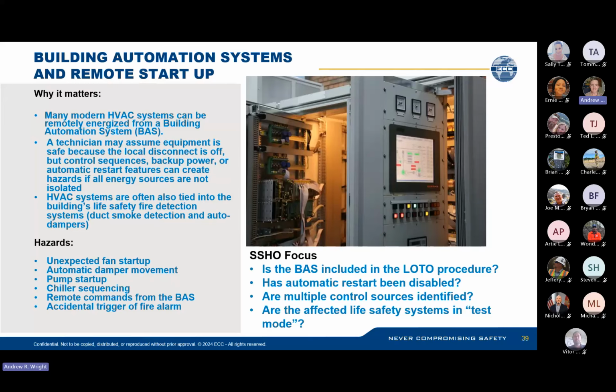HVAC systems can also be tied into the building's life safety system. A lot of times they'll have duct smoke detectors that will trigger if there's a fire, and they'll automatically shut all the dampers so that they're not pumping smoke throughout the building. And if you're working on one of those and you set it off, the fire department will come, which I have learned firsthand. So if you're working on a system that is tied into the life safety system, put the system in test mode so that you're not going to get the fire department showing up at your job site, because they're usually not happy about that. If you have an automation system, make sure that's included in the lockout/tagout procedures, and that whoever is operating that system is aware of what's going on.